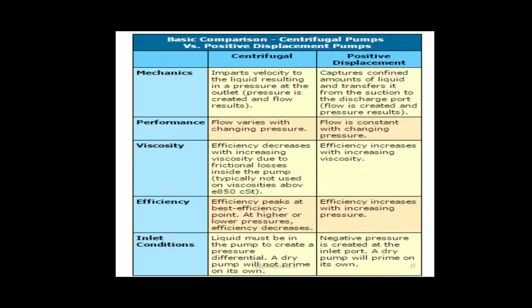There will be a basic comparison between centrifugal pumps versus positive displacement pumps. In mechanics, centrifugal pumps impart velocity to the liquid resulting in pressure at the outlet, or pressure is created and flow results. But positive displacement pumps capture confined amounts of liquid and transfer it from the suction to a discharge port. There are a lot of basic comparisons between centrifugal pumps and positive displacement pumps as shown in the figure.